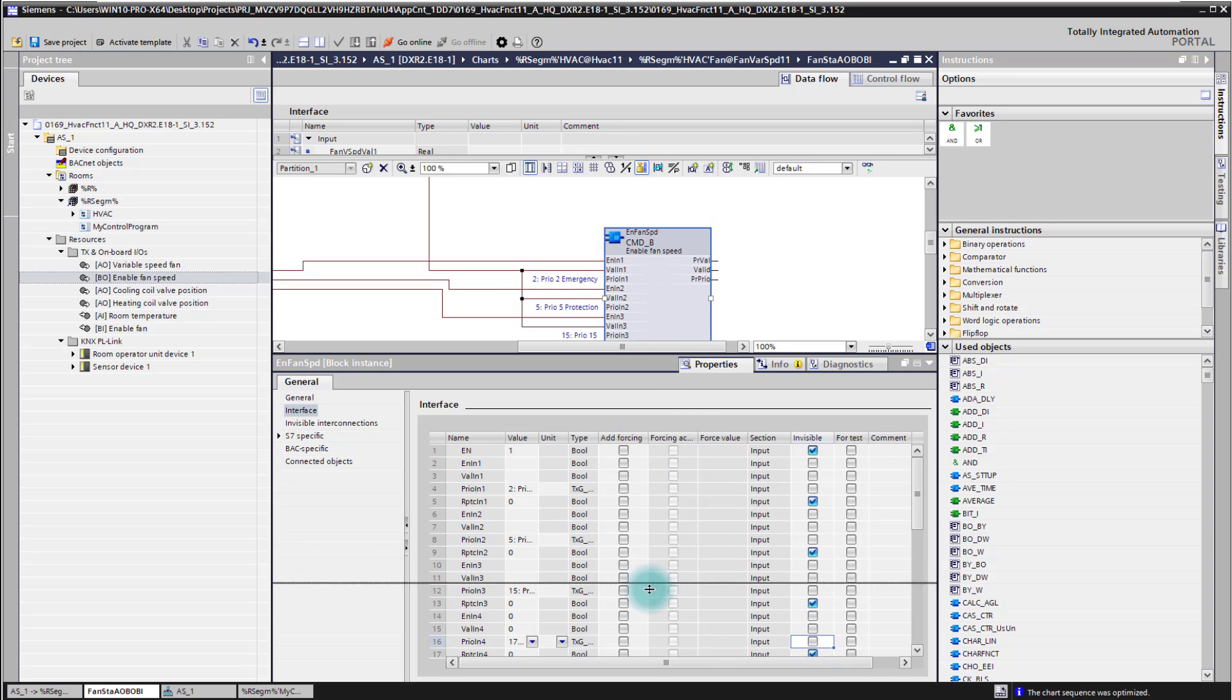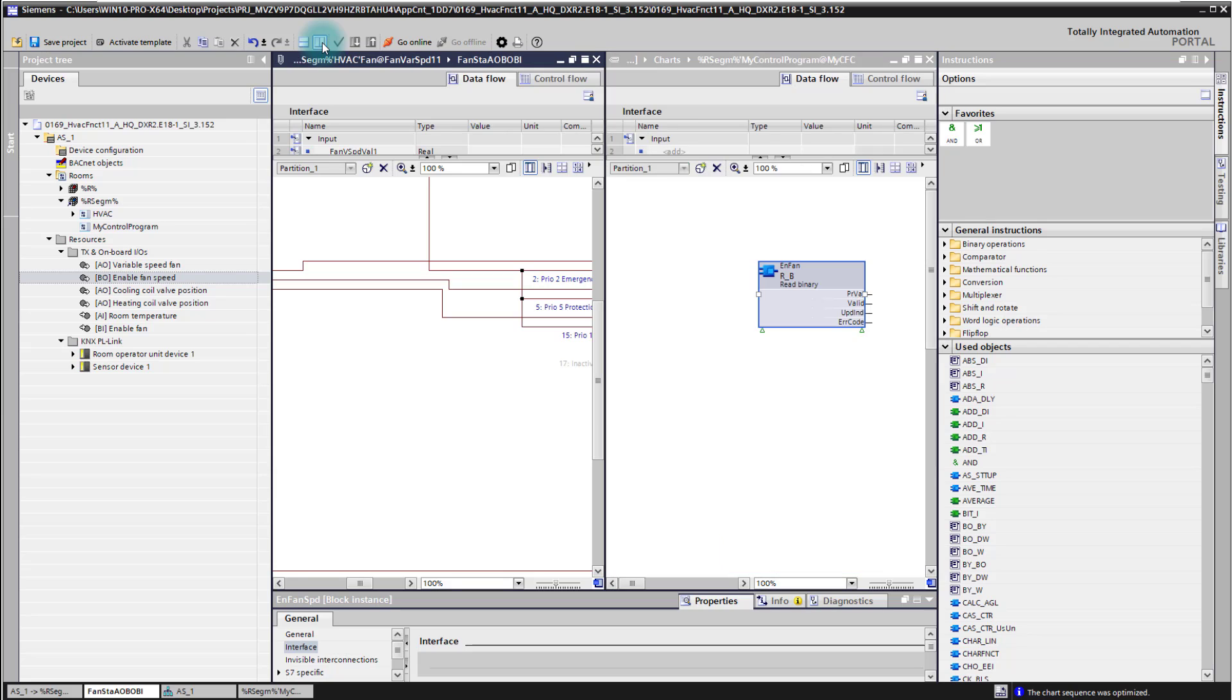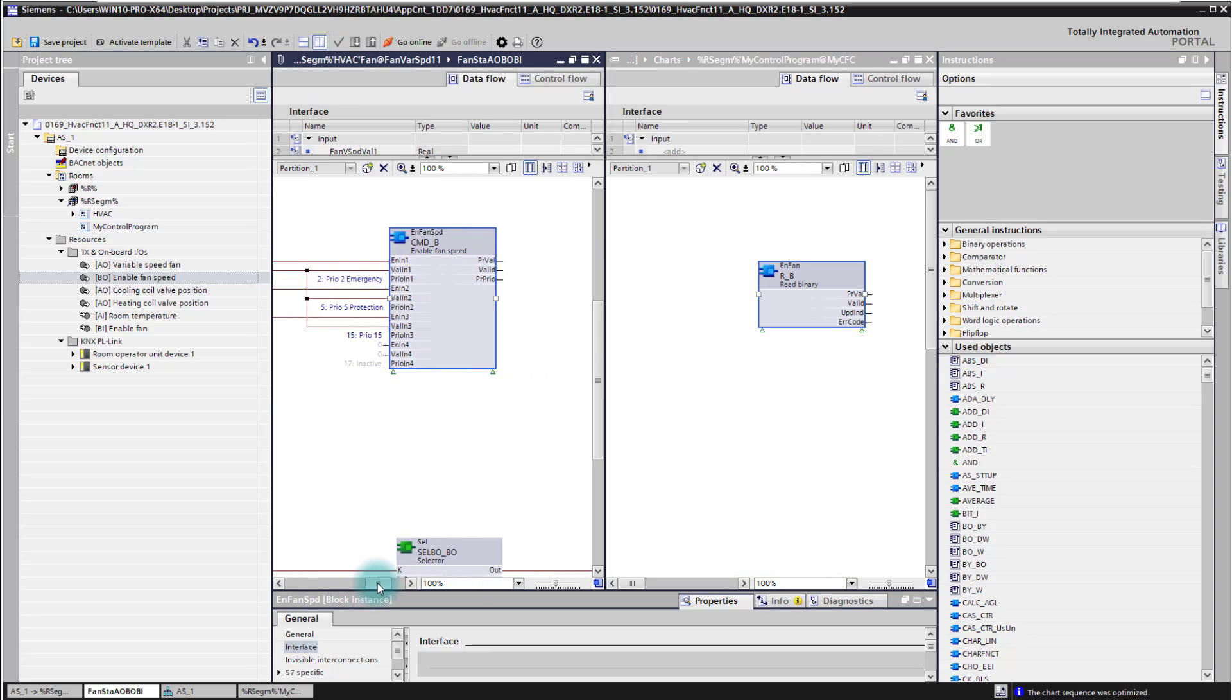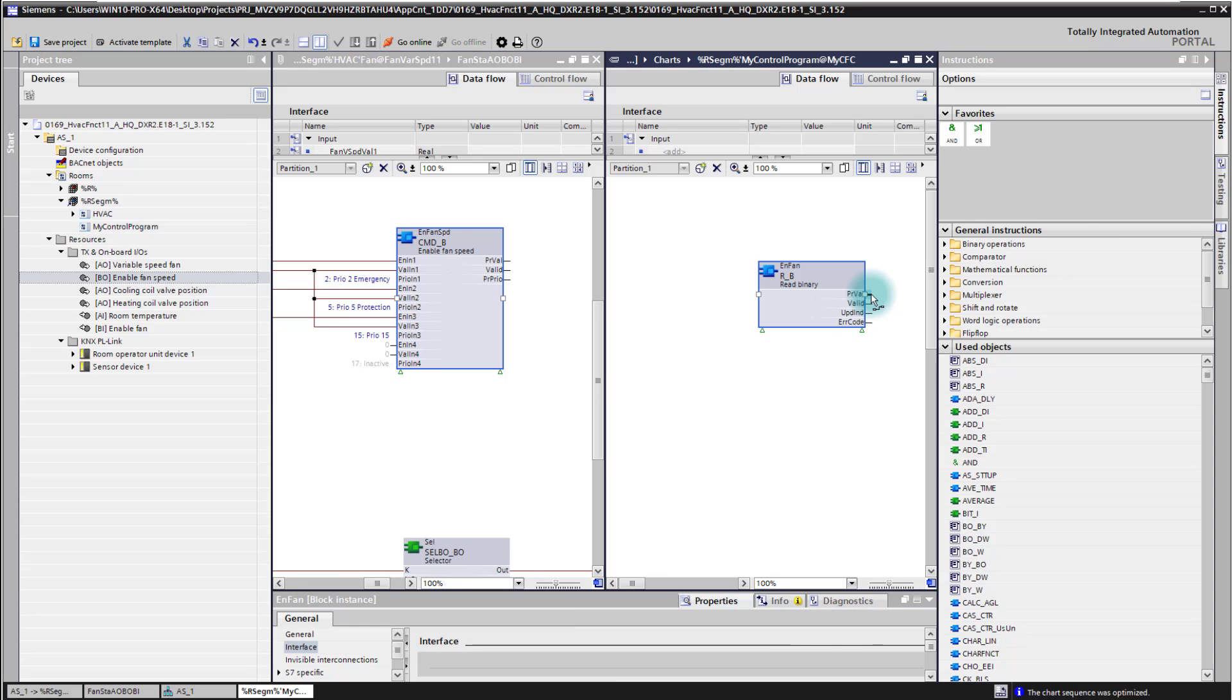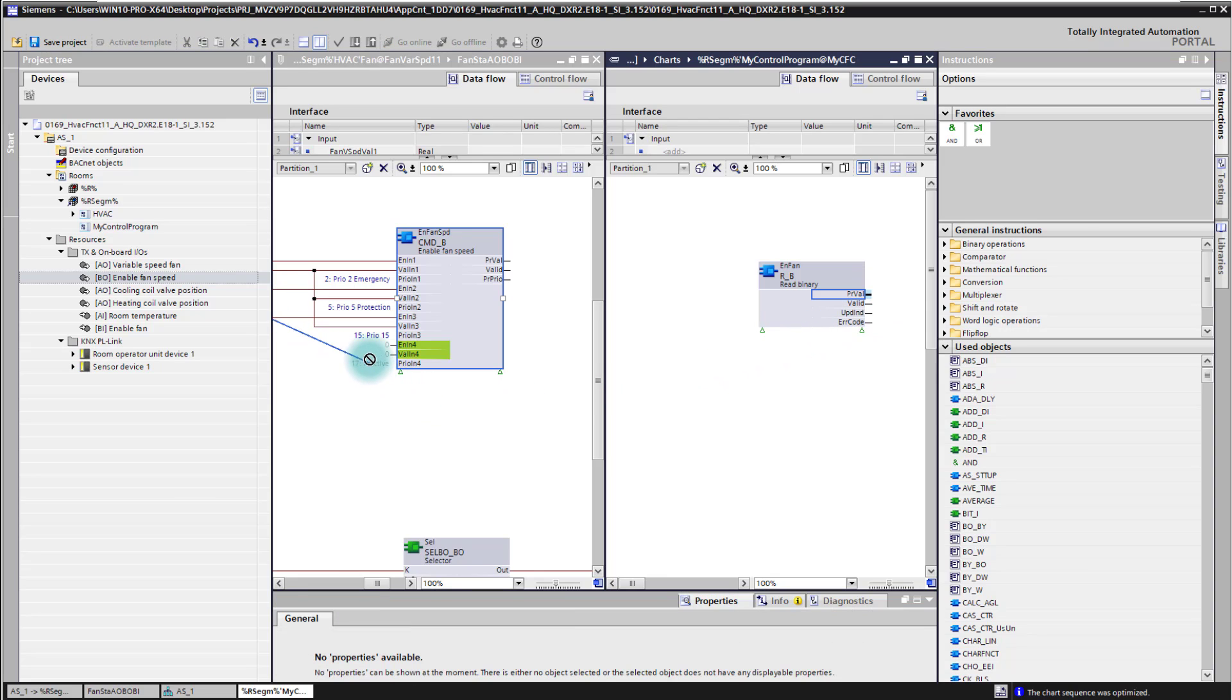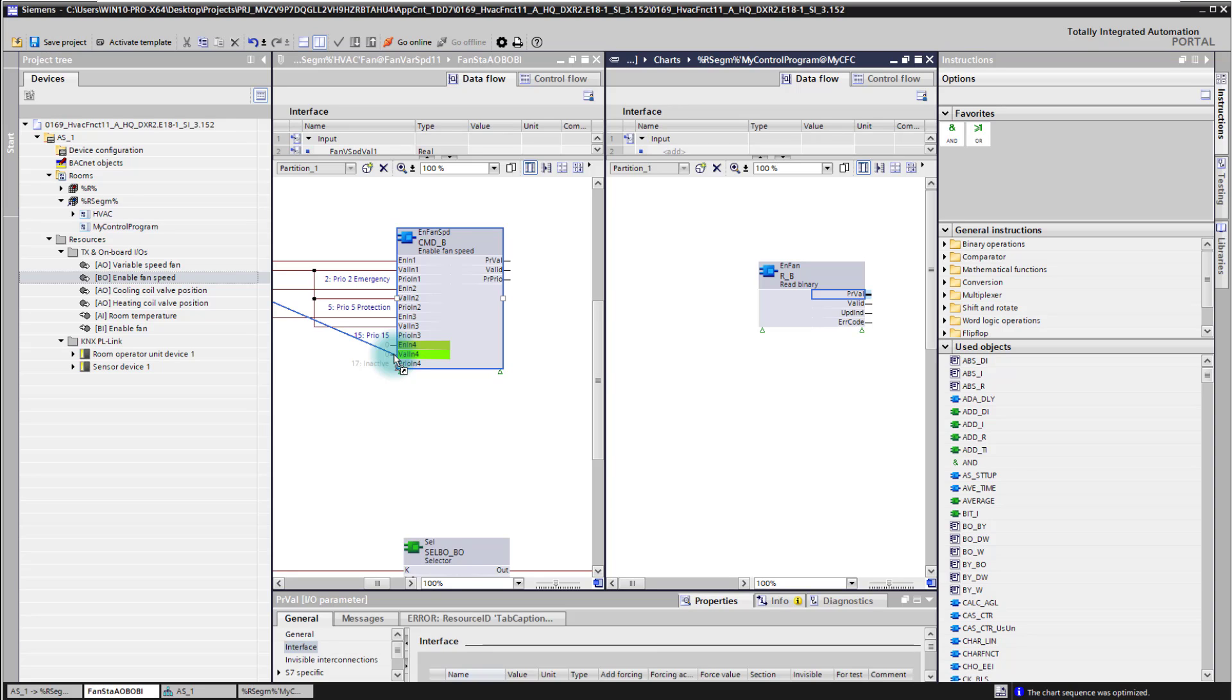And now we are ready here to connect our input signal. To connect a CFC block from another chart to this chart we simply split the window. We see now here on the left side the fan speed block. Here we see our enable block. And now we simply go to one of the pins, for example the process value pin, and we click it. I drop it over here to the other chart and just drop it here on the value input pin of number 4 of that fan speed block.